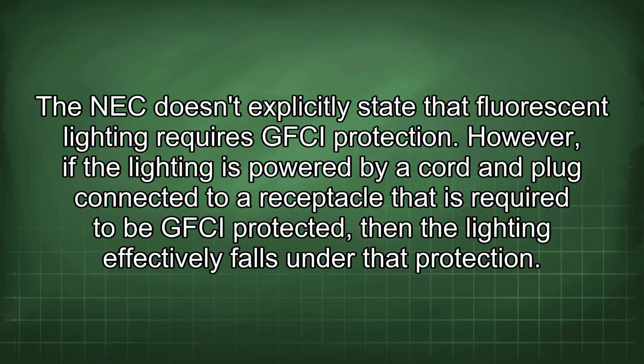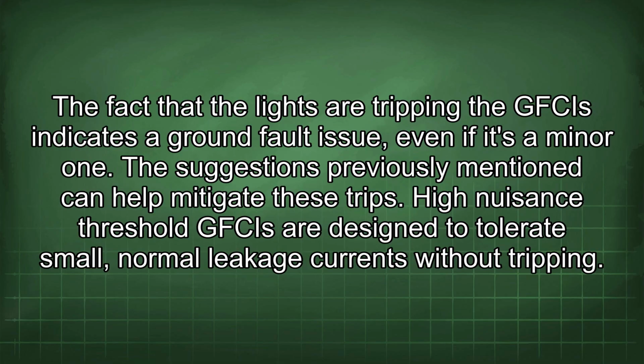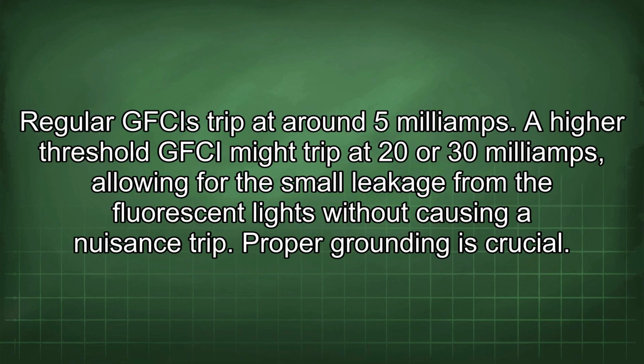The NEC doesn't explicitly state that fluorescent lighting requires GFCI protection. However, if the lighting is powered by a cord and plug connected to a receptacle that is required to be GFCI protected, then the lighting effectively falls under that protection. The fact that the lights are tripping the GFCIs indicates a ground fault issue, even if it's a minor one. The suggestions previously mentioned can help mitigate these trips. High nuisance threshold GFCIs are designed to tolerate small, normal leakage currents without tripping. Regular GFCIs trip at around 5 mA. A higher threshold GFCI might trip at 20 or 30 mA, allowing for the small leakage from the fluorescent lights without causing a nuisance trip.